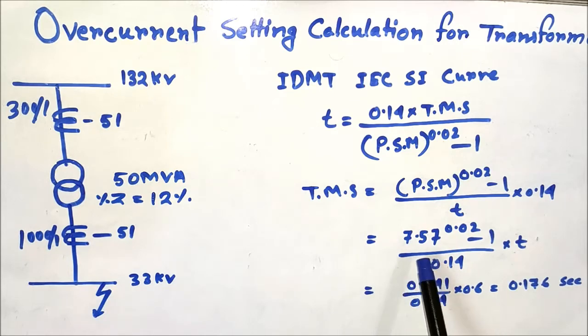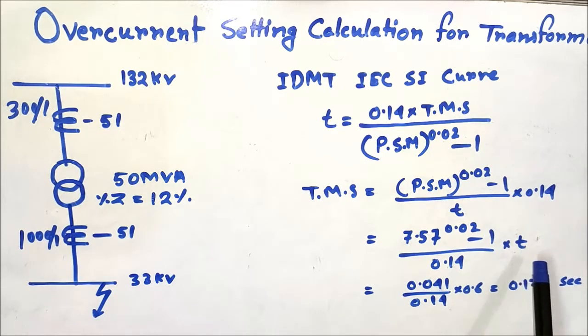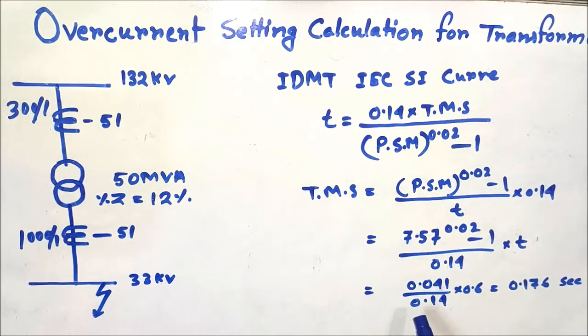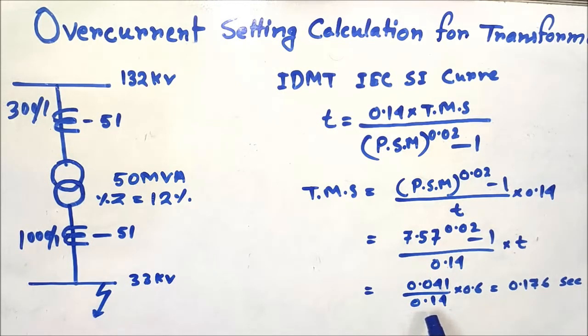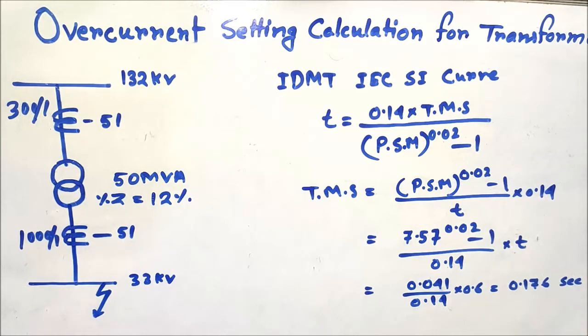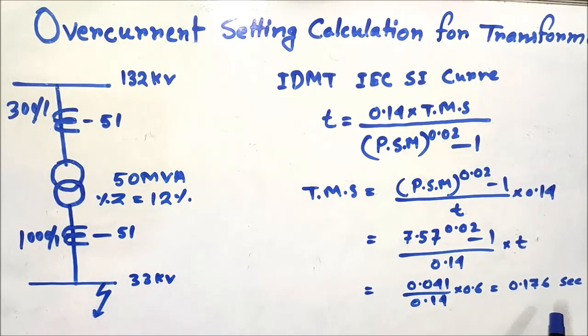Substituting values: PSM is 7.57, so 7.57^0.02 − 1 equals 0.041. Then TMS = 0.041 × 0.6 / 0.14, which comes to 0.176 seconds. So the time multiplier setting for the LV overcurrent relay (51 LV) should be approximately 0.176, or you can round it to 0.18.